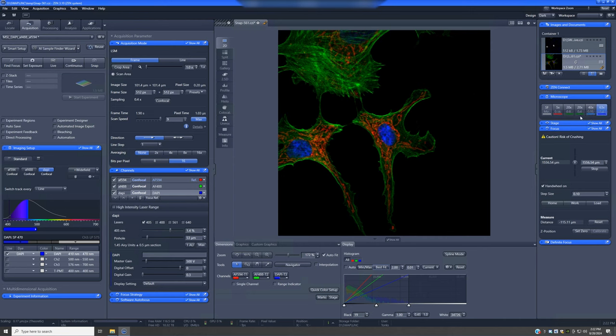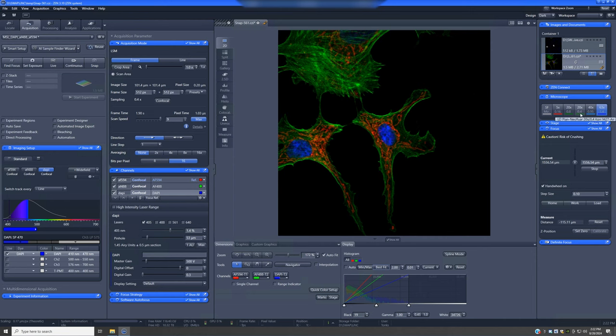The 20x0.4 is a specialized objective that is compatible with plastic multi-well plates. So if you use plastic multi-well plates, you should use this objective and only this objective aside from the 5x, which I'll discuss in a second. It also is compatible with something called Plast DIC, which is a form of contrast enhancement that is compatible with plastic and gives results similar to DIC. So if you're trying to image things through plastic plates, this is a good option.